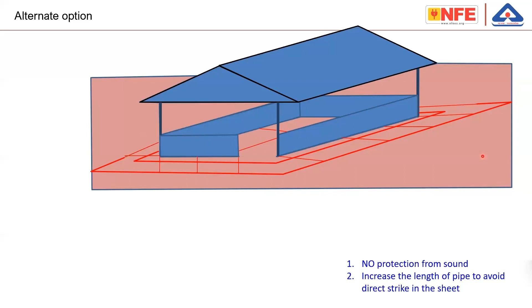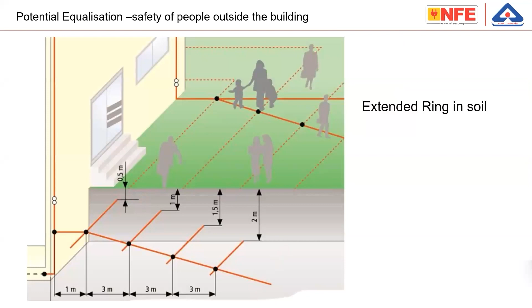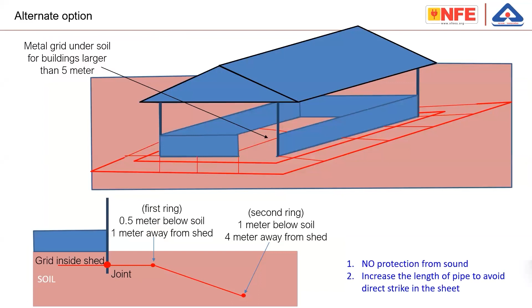So if you want to protect a thatched roof, the only way is to make ring earthing. Also, please note that if you want to protect any place against step potential, the idea is to make a ring conductor all around the area, including potential equalization, like extending the ring, which I have shown in one of the pictures. Let me show that picture again. So even in a well-protected building, by extending the ring, you can make equipotentialization so that people outside the building are safe. A similar arrangement may be made to protect people outside this particular shelter.